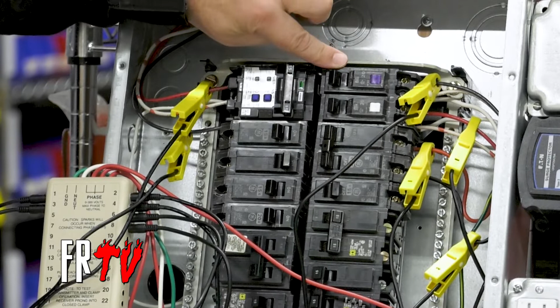Sure. So what we were trying to show is different examples of the various components inside a breaker panel, and also highlight some new technology, like AFCI. This is an example of an AFCI breaker — this one has both AFCI and GFCI functions. This is a GFCI breaker. We also have a smoke alarm here, plus a visual indicator for folks with hearing aids, and a surge protector that protects the whole system.